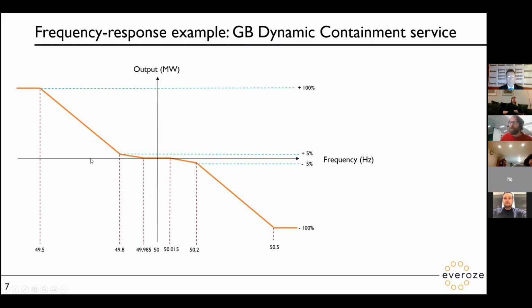So, output power. Batteries aren't just exporting, they're also importing. Below this horizontal line we've got imported power. So say it's a 10 megawatt project, we might be able to export at 10 megawatts up here, or import, charge up at 10 megawatts down here. On this axis we've got what the grid is doing, the frequency: in the middle, 50 hertz, out here 50.5, out here 49.5, much like the graph we looked at a moment ago.